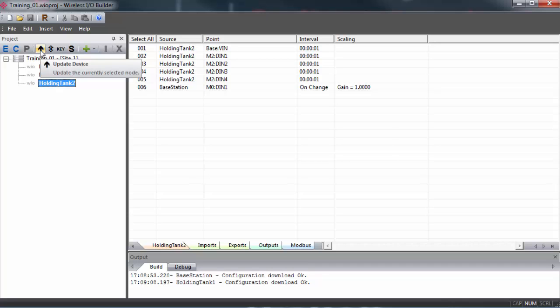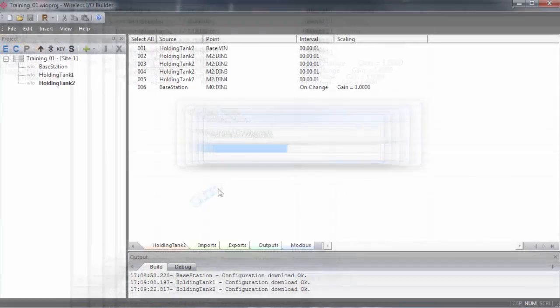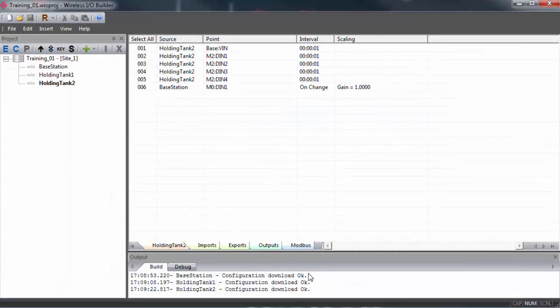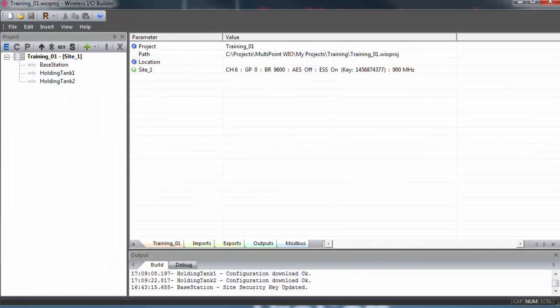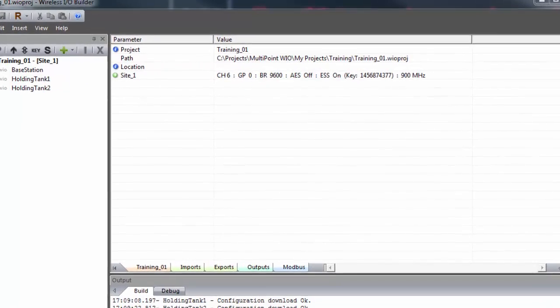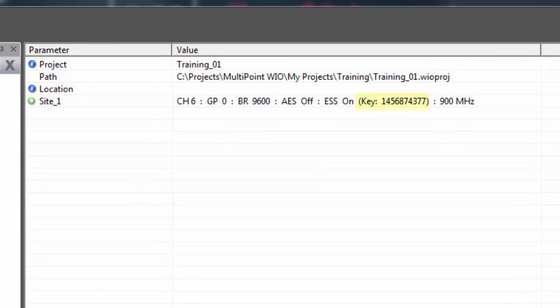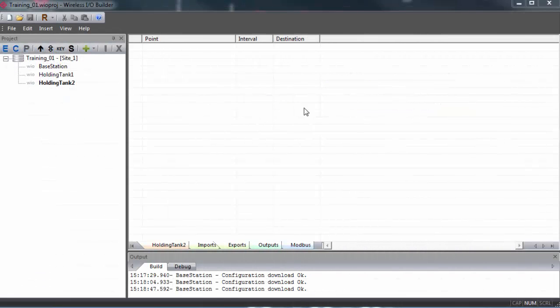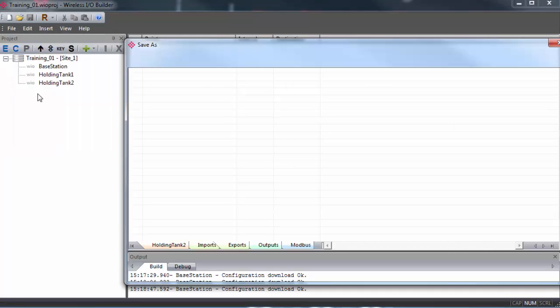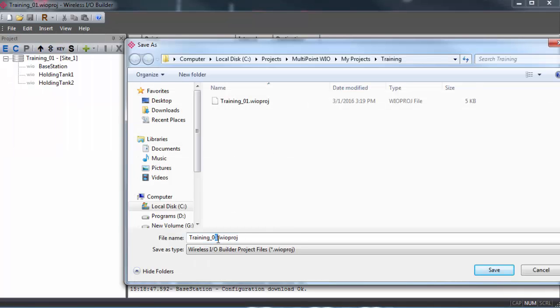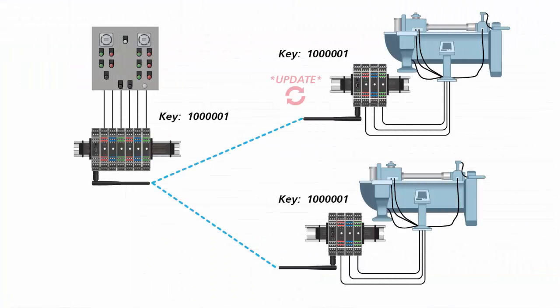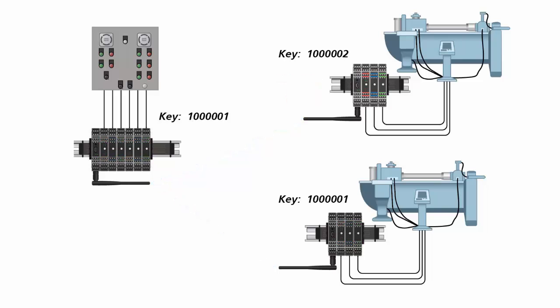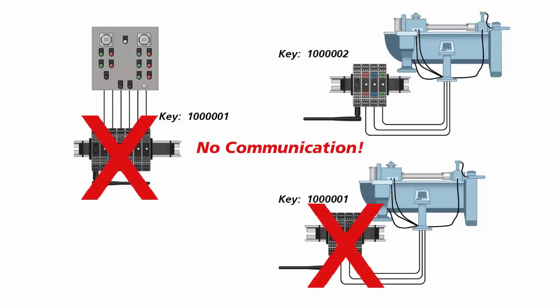An important thing to note is the site security key function. The multipoint wireless IO gateways are designed to only communicate with other multipoint wireless IO gateways that have the same security key in their configuration files. When you create a new project in ProSoft Wireless IO Builder, a new site security key is automatically generated, and every gateway that's updated with this project file will be assigned that security key. If you go up to File and select Save As, this will be regarded as a new configuration file, and it will generate a new key. Any groups within a network that are updated with this new file could potentially be assigned the new key and would then be unable to communicate with any other groups on the network.